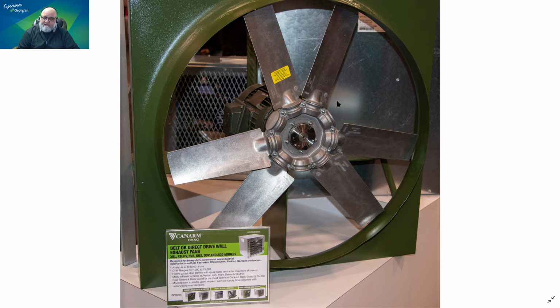Now, there's no duct here. And by the way, propellers should never be ducted unless they are designed to be ducted. If you put a duct here, as you already know from gas piping design and vent sizing, the flow of fluid in a conduit is going to experience resistance to flow.